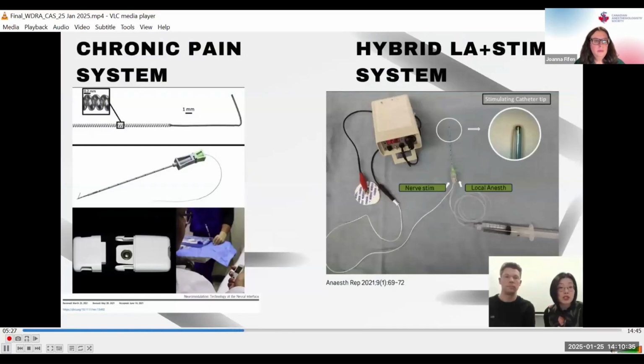Currently, there are 2 systems that can be used for peripheral nerve stimulation to treat acute pain. The one on the left is commonly used in chronic pain, and it is FDA approved for use in acute pain as well. A very fine lead is inserted through an introducer sleeve. It is then placed about 1/2 to 3 centimeters away from the target nerve percutaneously, with either X-ray or ultrasound guidance. The lead is then attached to an external stimulator, usually for several days or weeks.